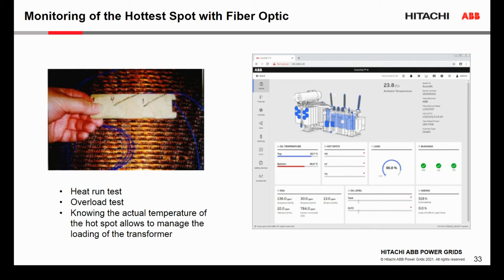Knowing this temperature, we can manage the loading of the transformer, and we can also connect the fiber optic to the monitoring system, which will allow us to calculate the loss of life, and also will allow us to load the transformer when we really need it in an emergency situation.